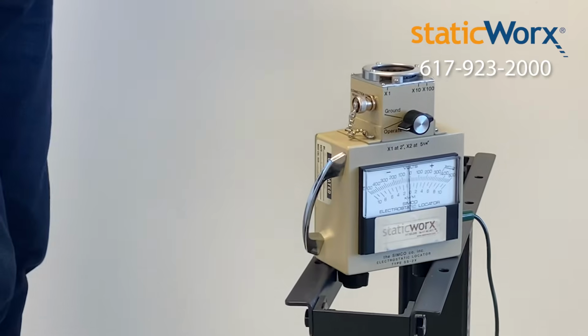Big difference. Rubber conductive flooring does not generate as much body voltage as vinyl. In fact, it's a factor of over 10. So when you're looking at flooring and you're thinking about what's going to happen when my people walk on the floor and they don't have heel straps on, that's the reason you want to gravitate towards a conductive rubber product instead of a conductive vinyl product. So resistance and body voltage don't necessarily correlate. And I think that's something you'll read in many, many articles, but I've just shown you that today.